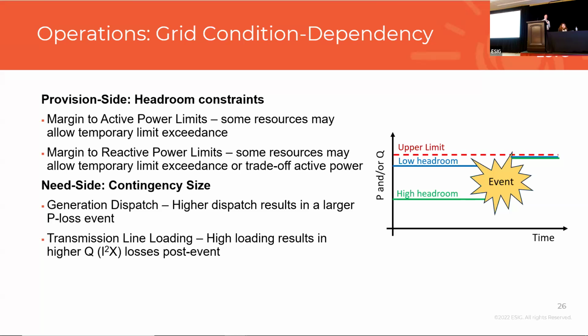However, there are differences in shorter time frames depending on the technology. In a synchronous machine, if you were at maximum power output and a disturbance happens, like a loss of generation causing a sudden change in frequency, you will still get a response in the short time frame because there's an energy supply available in the rotating mass. It's the actual mass of the rotating machinery that helps provide active power.